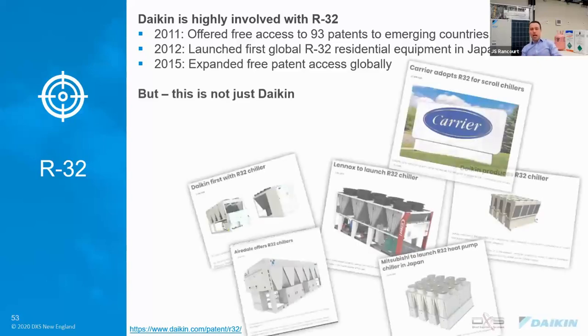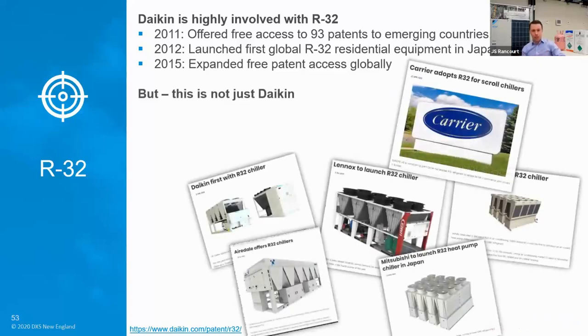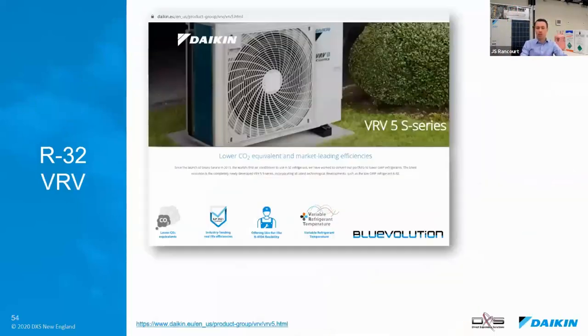And here's some snapshots of all sorts of other manufacturers, either chiller manufacturers and/or VRF manufacturers, that have released that they're using R32 in their machines, and they're already developing that because they're being used overseas where A2Ls are allowed, or they're being used in North America because chillers being outside the building don't need to follow all those ASHRAE rules of refrigerants inside the building. There's some limitations, but you're gonna start seeing R32 chillers in the US as well. Daikin is also developing those.